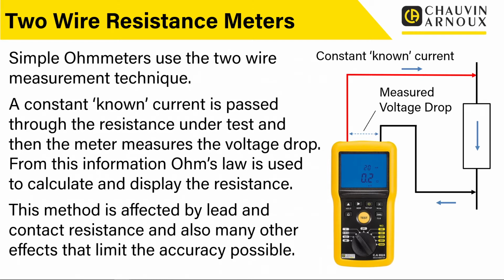Now, there are some drawbacks with this, and as we've said in the slide here, this method is affected by lead and contact resistance, and also many other effects that limit the accuracy possible. Because we're measuring the volts drop between the measurement terminals effectively inside the tester, the lead resistance and any contact resistance is included in the measurements. Now we can zero lead resistance, we can touch the leads together and zero those out, so we can account for that. But contact resistance is key on this as well, because where we make the connections between the probes and the material under test, we need to have really good, really clean contacts. And generally these measurements are usually carried out at quite low current, so 20 milliamps, 200 milliamps, those sort of levels.